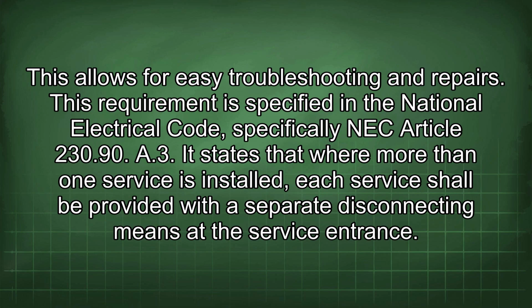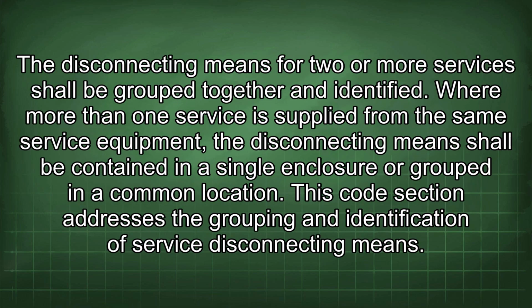It states that where more than one service is installed, each service shall be provided with a separate disconnecting means at the service entrance. The disconnecting means for two or more services shall be grouped together and identified. Where more than one service is supplied from the same service equipment, the disconnecting means shall be contained in a single enclosure or grouped in a common location. This code section addresses the grouping and identification of service disconnecting means.